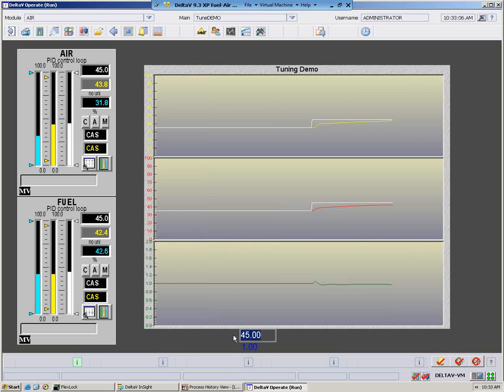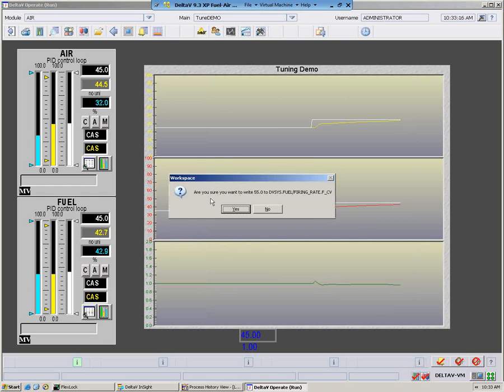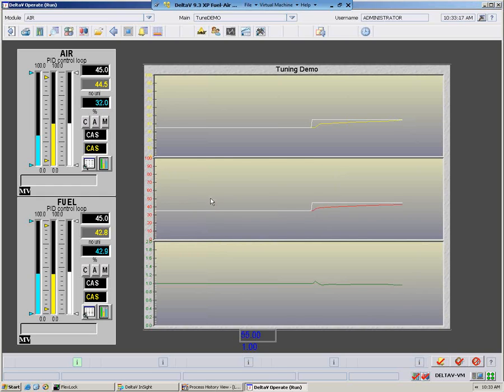So he's adjusted the reset of 1 to speed it up a little bit, changing the firing rate. And now you can see that 1 is much faster, but that's not necessarily helping our green line that's down there. So let's see where Kurt takes us next.